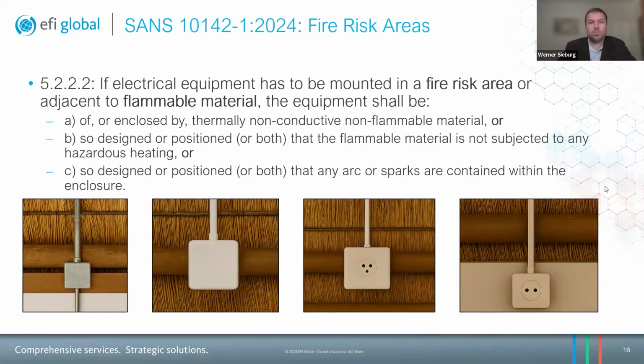And we'll start with section 5.2.2.2, which states that if electrical equipment has to be mounted in a fire risk area or adjacent to flammable material, and just quickly to pause here, thatch is both a fire risk area and a flammable material, and so both of them apply, it shall be of or enclosed by thermally non-conductive and non-flammable material.